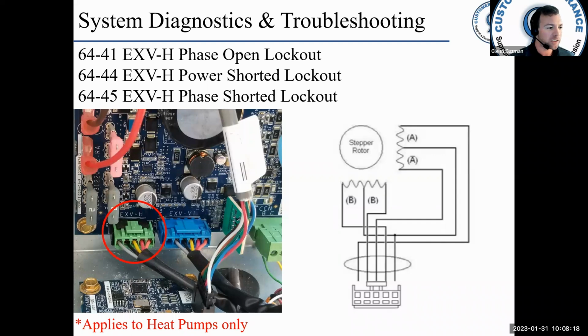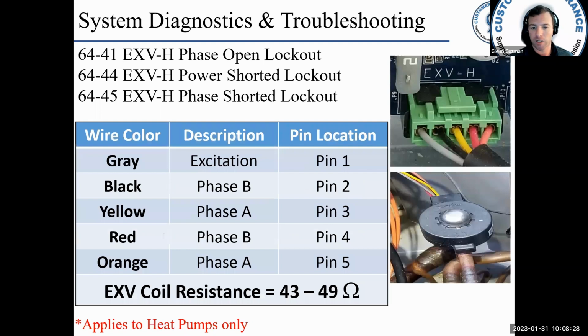The EXV coil resistance should fall between 43 and 49 ohms when measured from common to any one of the remaining terminals. Okay, so you can see here, gray in this case is your excitation, which is common. And then from pin 1 to 2, or 1 to 3, 1 to 4, 1 to 5, you get it. You should have somewhere between 43 and 49 ohms. 6441, the phase open lockout.